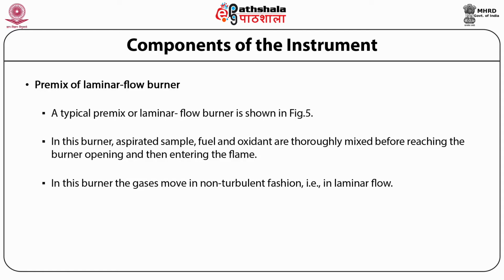An important feature of the laminar flow burner is that only a small portion, about 5% of the sample, in the form of small droplets, reaches the flame and is easily decomposed. By easy decomposition, it means that an efficient atomization of the sample in the flame will take place.